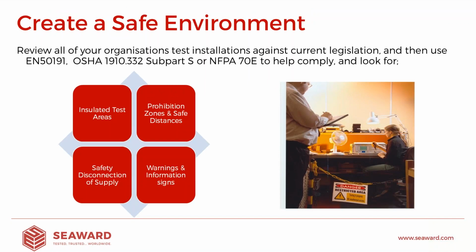So before you start creating a safe working environment, we need to look at these guidance documents to help us comply with the requirements within. But ultimately, what are we looking for? Well, there are four main areas that we really should focus on. The first one being, do we have insulated test areas? The second one being, do we have a safe method of disconnecting the supply in the event that something does go wrong? Have we set up things like prohibition zones and safe distances? And do we have sufficient warnings or information to alert people to the function of the actual area itself?